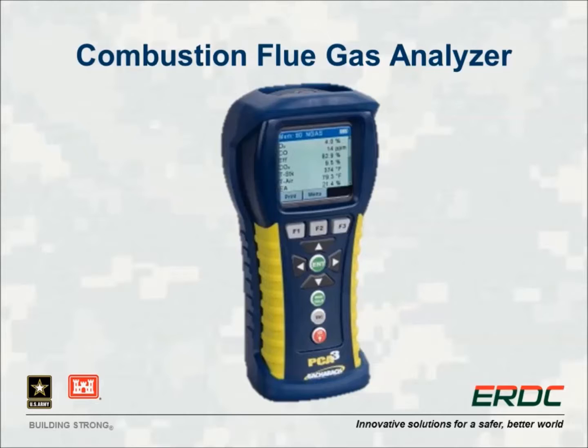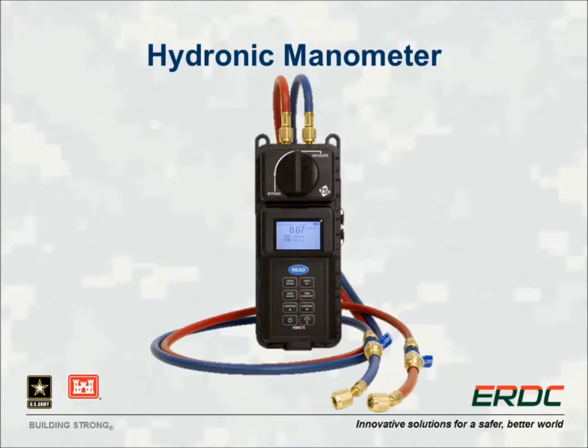Hydromanometer to do pump testing. You can determine where on the pump curve that pump is currently operating, and a lot of this would have to do with balancing operations as well, and being able to check those, determine if throttling is needed or any other changes to that pump.